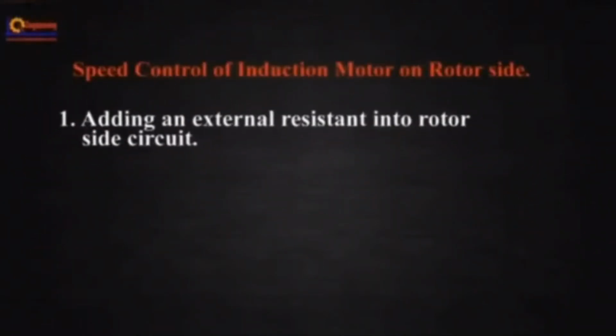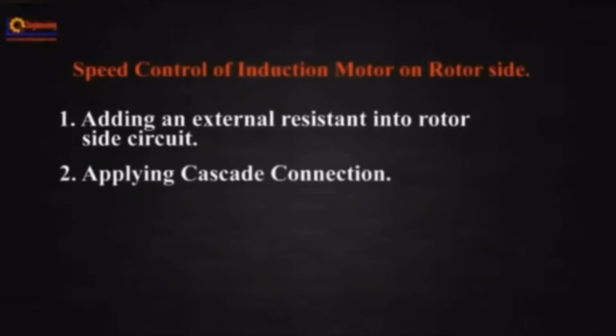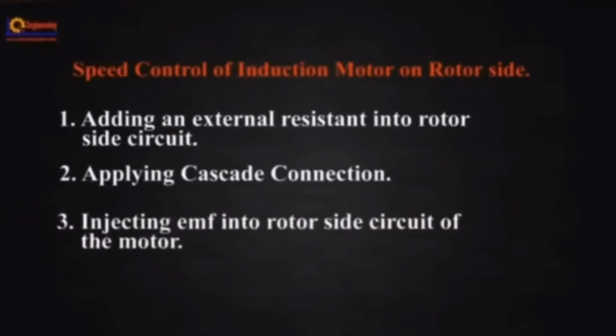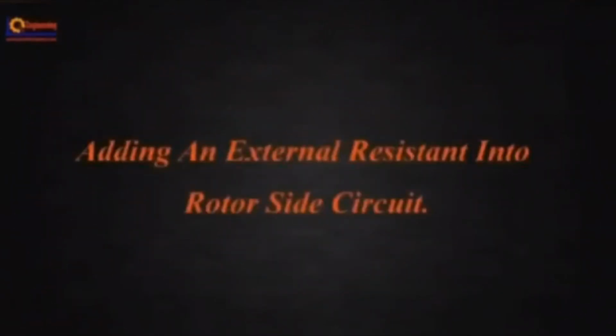The speed control of an induction motor by controlling the rotor side can be subdivided into several speed controlling methods, such as adding an external resistance into the rotor side circuit, applying cascade connection, and injecting EMF into the rotor side circuit of the motor. Adding an external resistance into the rotor side circuit.